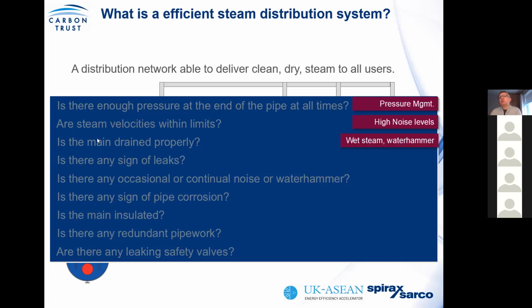Again, we talked about mains drainage, the wet steam, eliminating water hammer, leaks. What you'll find is that the quality of steam, which we mentioned earlier about the chemicals and the oxygen, means that if your steam is acidic because there's oxygen in it, you may find you have a lot of leaks in your system. And what you could find is that the reason why you have leaks is that the feed water tank or the deaerator is not doing its job. So in other words, where you have indications of leaks in your system, it's potentially because of steam quality. And again, we talk about water hammer, the trap stations. Are there issues of pipe corrosion? Again, water quality, treatment, deaerator operation.